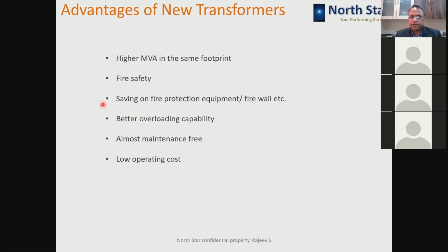Better overloading capability. You can load the transformers up to higher levels. They are maintenance free. The frequency of filtration is much longer, and you don't have to worry about it. And because the filtration frequency is low, the operating cost of these transformers is also low. So you save on that. If you calculate the total ownership cost compared to a mineral oil transformer, you will find it is almost the same, slightly higher compared to mineral oil.